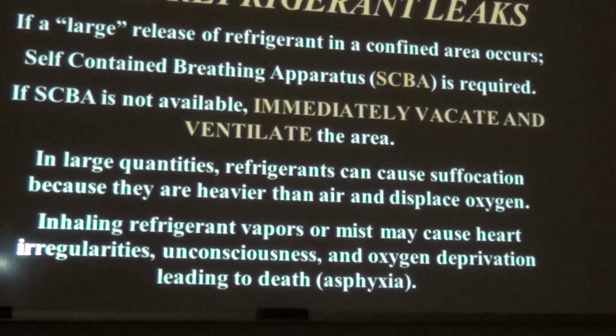Now, safety having to do with release of refrigerant. One of the qualities of refrigerants is that all refrigerants, I believe I'm right in saying this, are heavier than air. Because they're heavier than air, they're going to displace the air in a room. If you're in a mechanical room in a building or in a basement space, a confined space of any kind, and there's a refrigerant leak, it's going to push the air out and you're not going to be able to breathe. So, they're saying that what you should have by law is a self-contained breathing apparatus. However, recognizing that there are not many self-contained breathing apparatuses around, you are to immediately vacate the confined area and then ventilate the area.